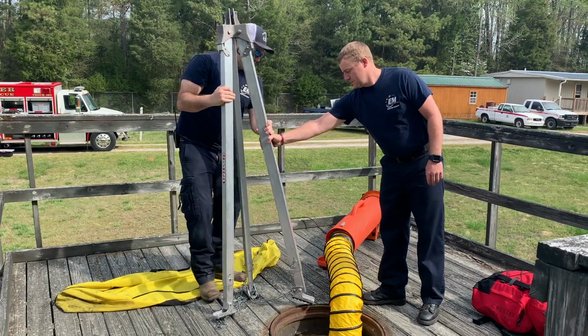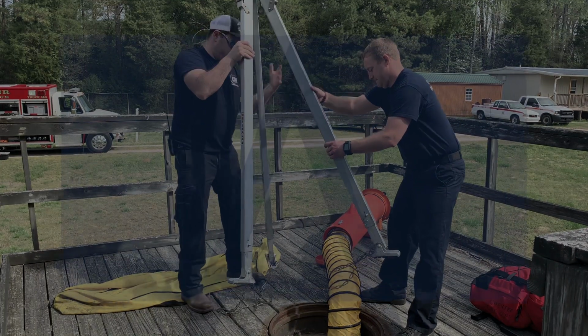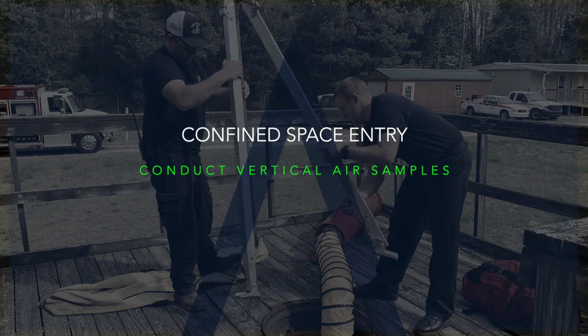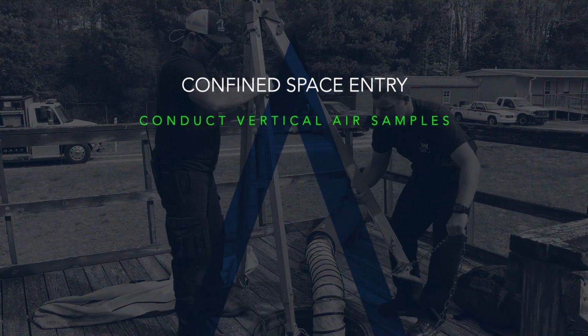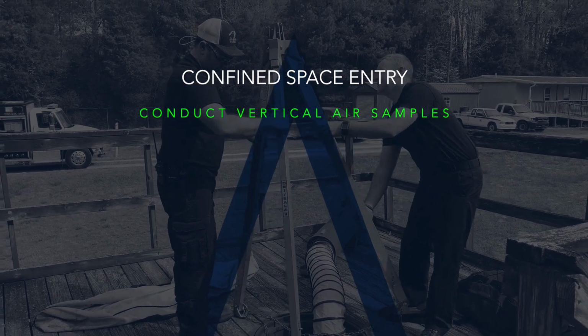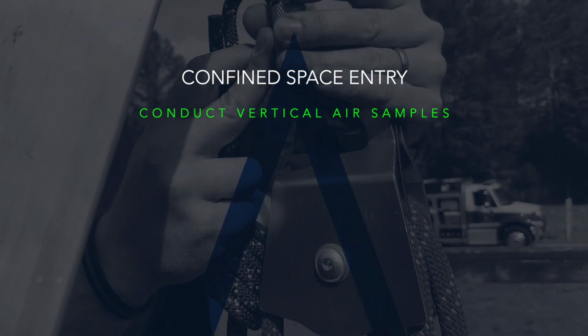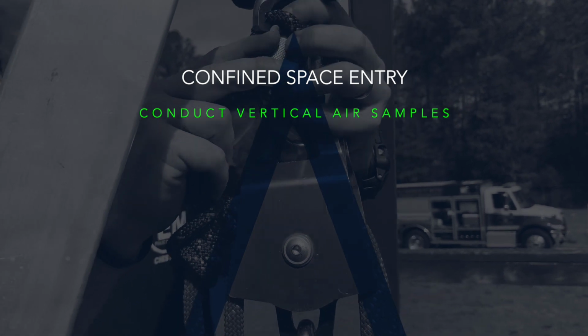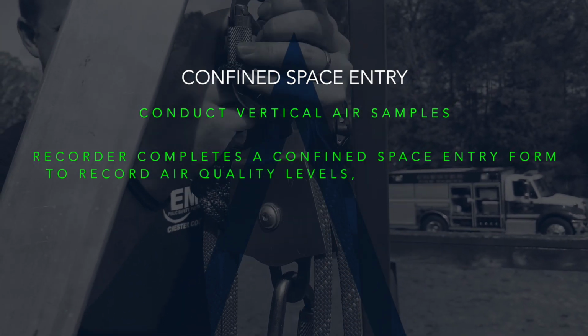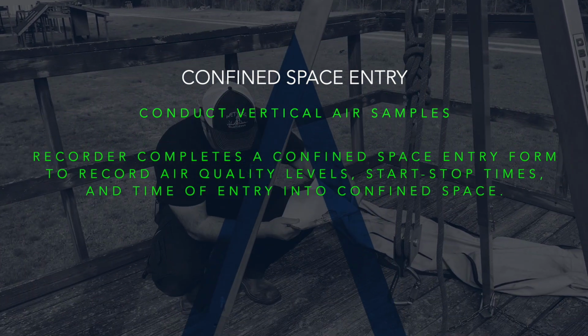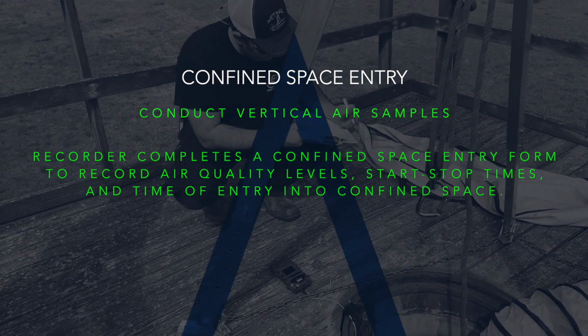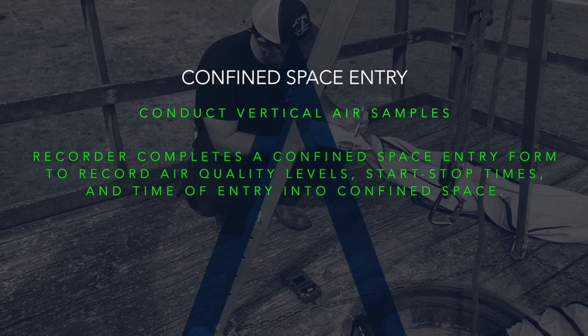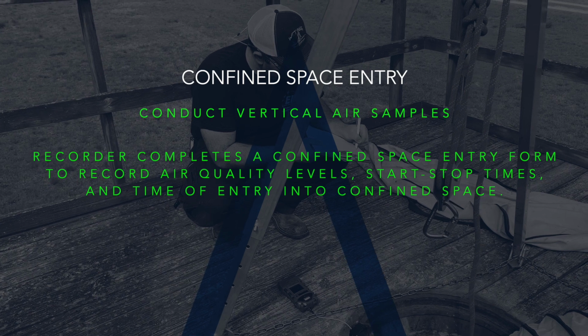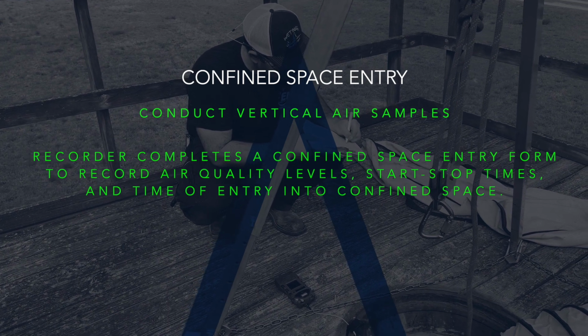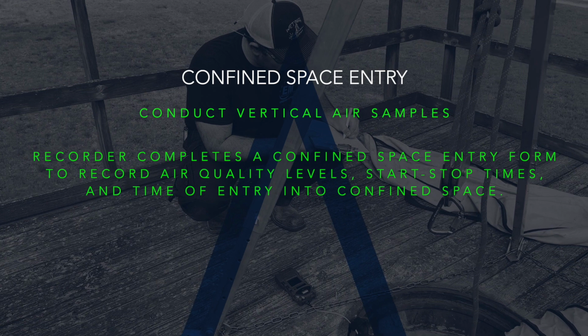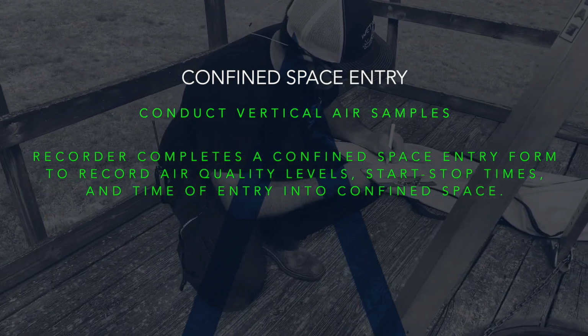Here's an overview of using the gas detector during confined space entry. Use the probe and line accessory for vertical drop air sampling. Sample the air at the top, middle, and bottom of the space for a minimum of 30 seconds at each level. Have a scribe record the following: the start time and air level at the start of monitoring, the air quality reading at each level, top, middle, and bottom. Record air quality at 5-minute increments. And finally, the time of entry into the confined space.